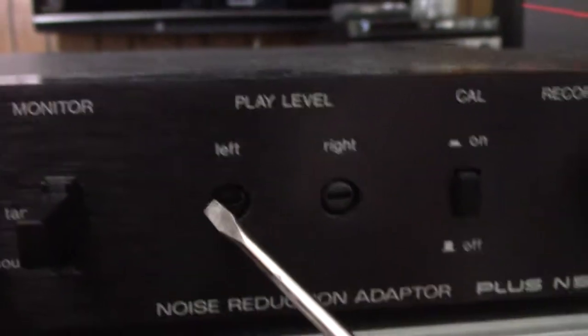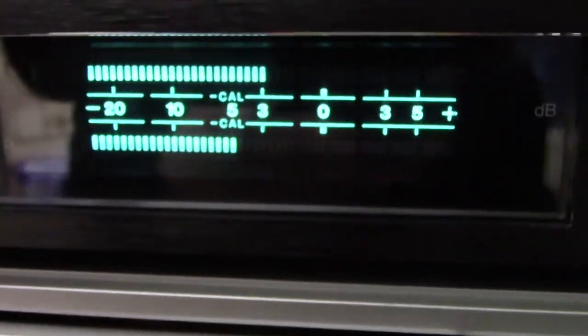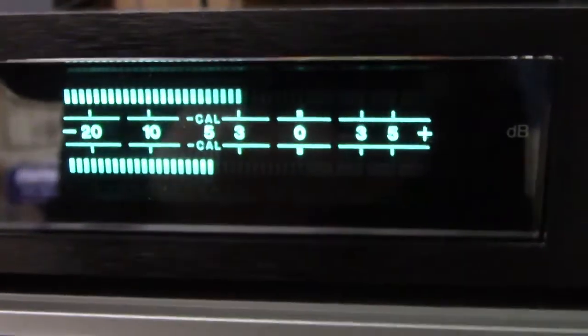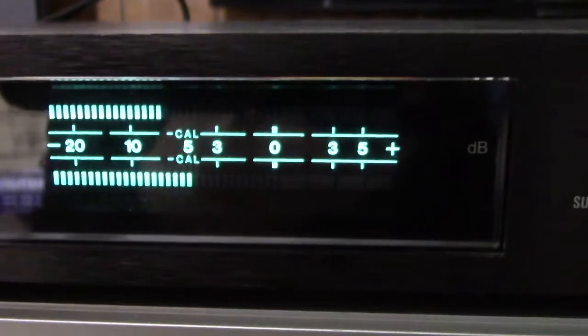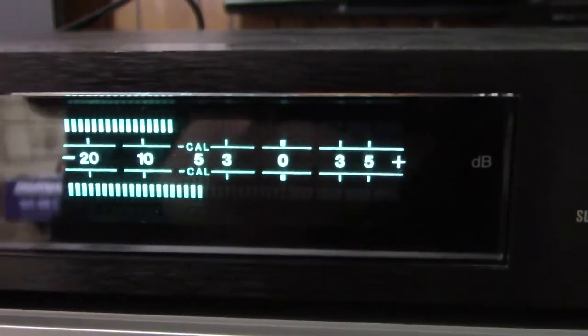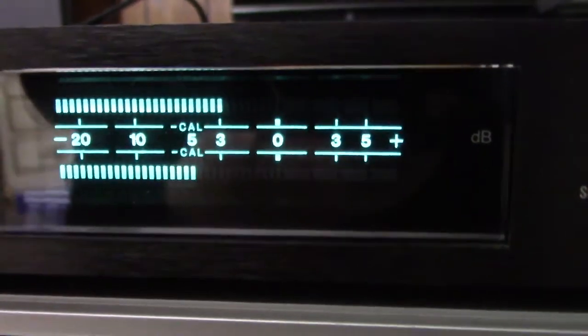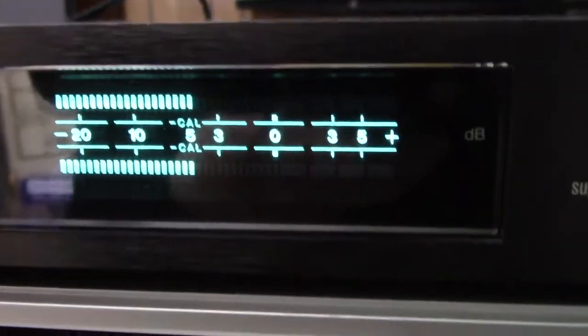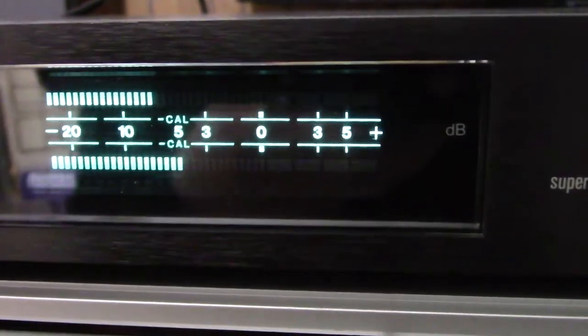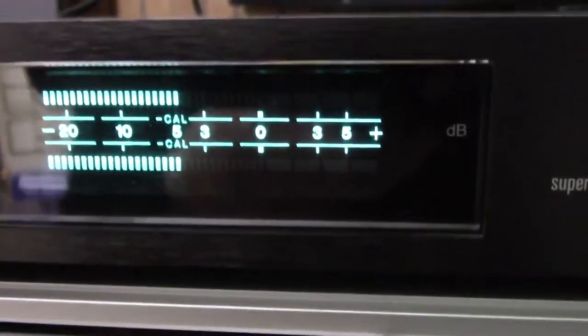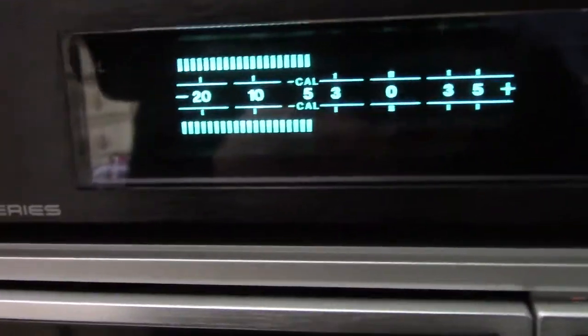and there are adjustments for those displays. These guys right here, these play levels. What you've got to do is tweak them so that it lines up with cal. And you see they kind of get bumpy here, so you can take it all the way down, or you can put it all the way over, quite a bit over if you want, but no, you want it right on the cal right there. And that's a good spot for that one. And the other one is already in cal, so we're going to leave it there.